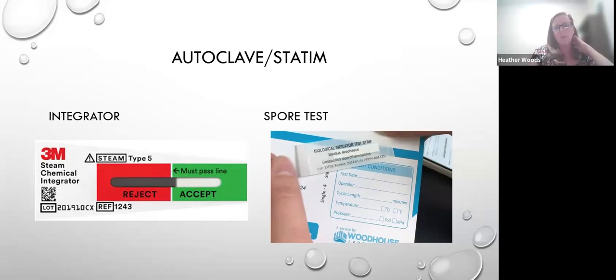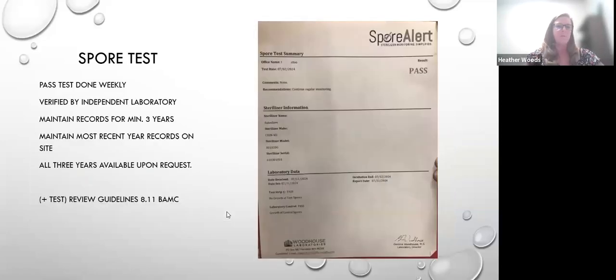And there are different types of integrators. Like this one, it shows that it hit the pass line. And reiterating what Michael said, make sure that it met all the parameters. There's no damage to the packaging, the packs, there's no water or anything like that. And it has also met the criteria in the pass line. Otherwise, rerun the cycle again. This is an example of a spore test.